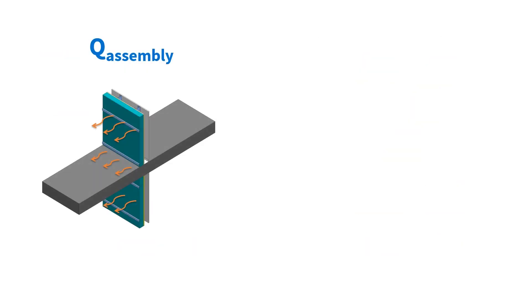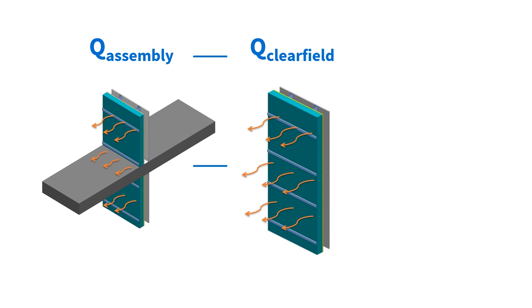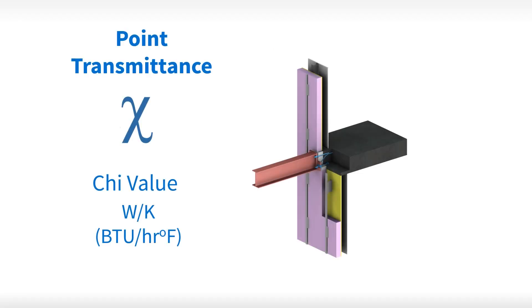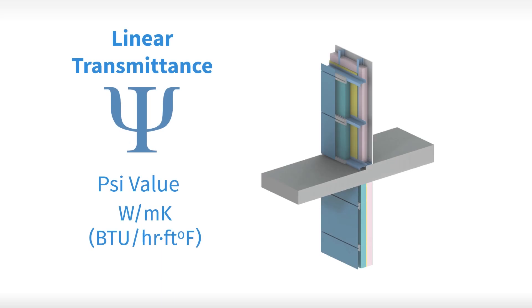Performance of a transition detail is determined by taking the full heat flow through an assembly with the detail present, and subtracting out the heat loss through the assembly if there were no detail. This leaves just the heat flow caused by the transition detail. For point details, that heat flow is left as is and called a chi value. For linear details, we turn it into a heat flow per length, called a psi value. By separating out the performance of these details from the clear wall, we can simplify our calculations greatly.